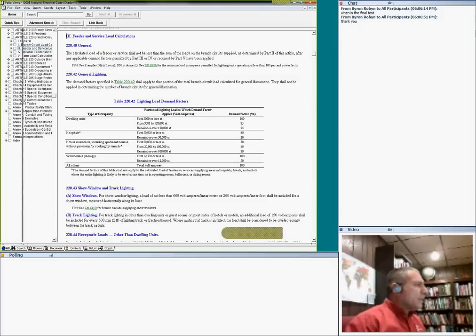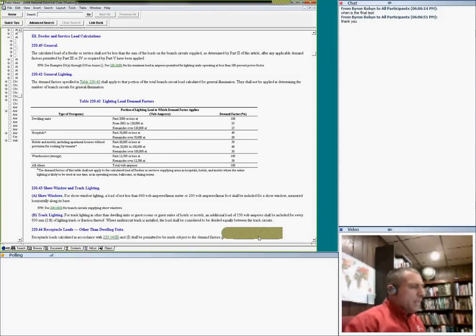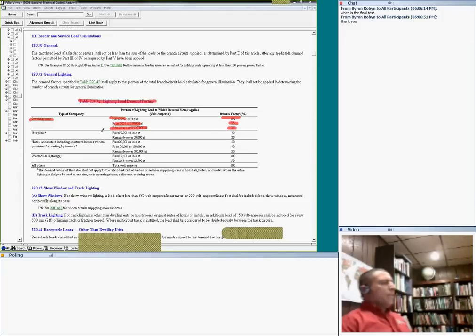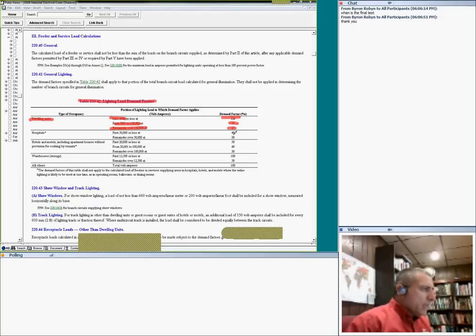Then the second thing I want to go over, guys, is the demand. There is a demand table. After you calculate your volt-amps, here's the one for dwelling. The first 3,000, you leave alone. Anything higher than 3,000 up to 120,000, multiply by 35 percent. Anything higher than 120,000, multiply by 25 percent. First one 35, the second one 25, and the first 3K leave alone. This is called the demand factor, guys. Very important to apply the demand factor.